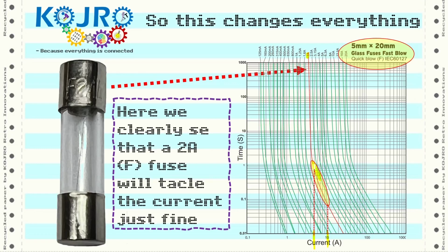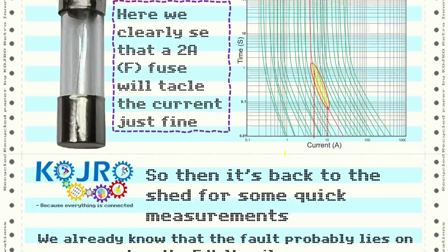That means this fuse would actually survive because the current draw we have is in this window here. So when we dug deeper into this, we saw that the theory behind this and my thinking was dead spot on from the start, but it was based on one false pretense - the original 1.6 amp fuse, and not a 2 ampere fuse with a different characteristic.